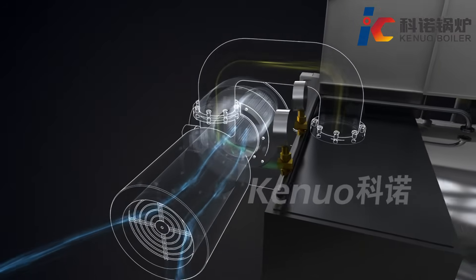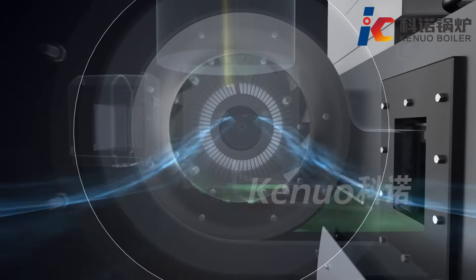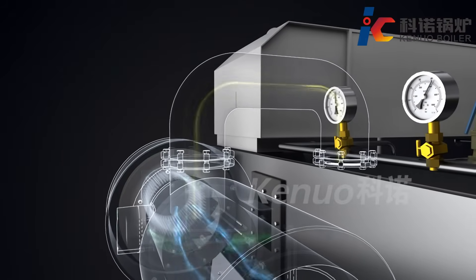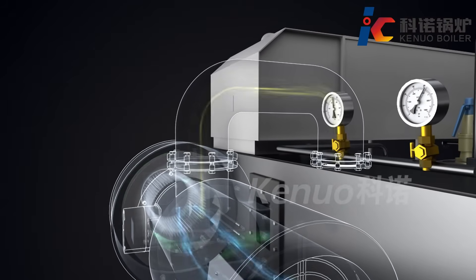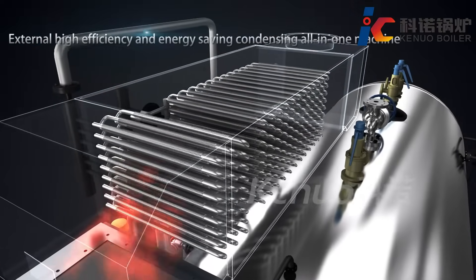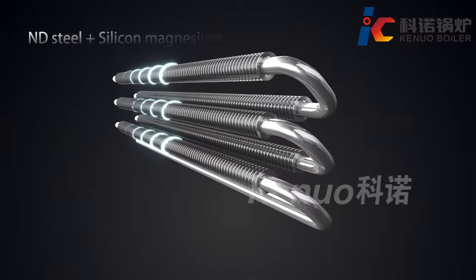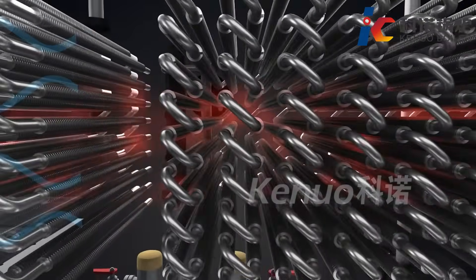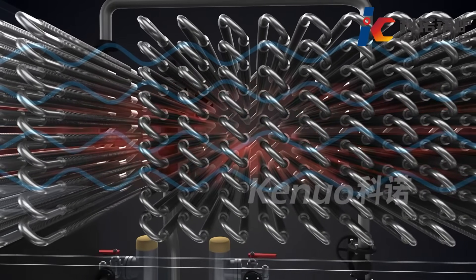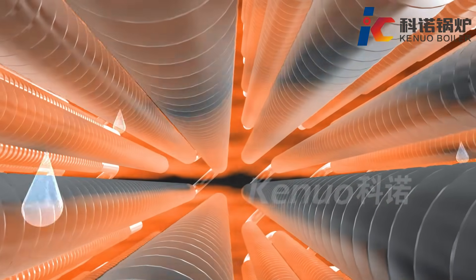An overhead cantilever fan provides accurate air pressure and volume, with a silencer included. Built-in flue gas recirculation technology makes nitrogen oxide emissions less than 30 mg per normal cubic meter. The external integrated economizer and condenser are made of ND steel plus silicon-magnesium-aluminum alloy finned tubes in staggered arrangement.